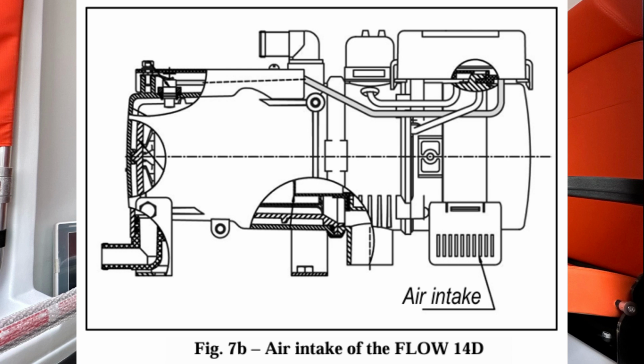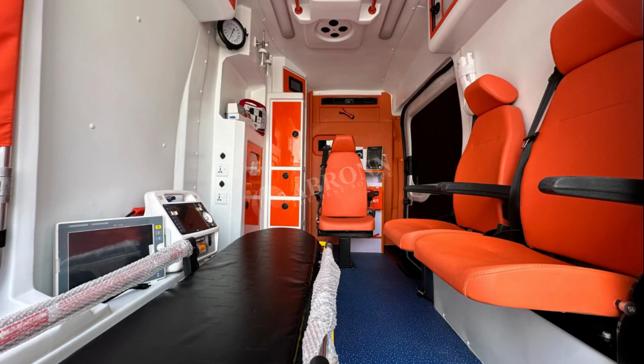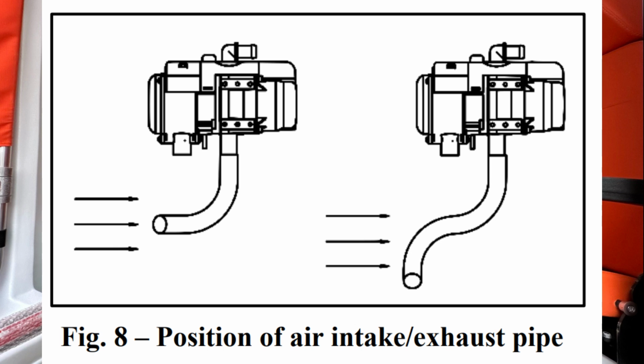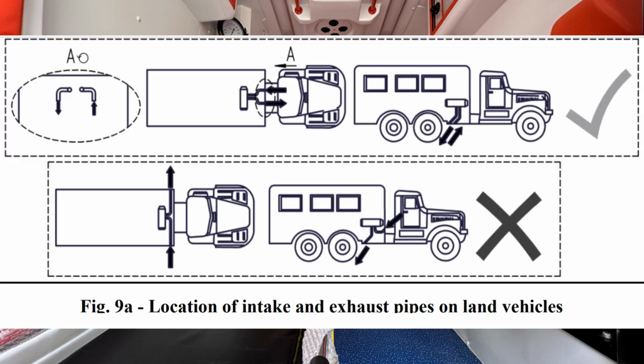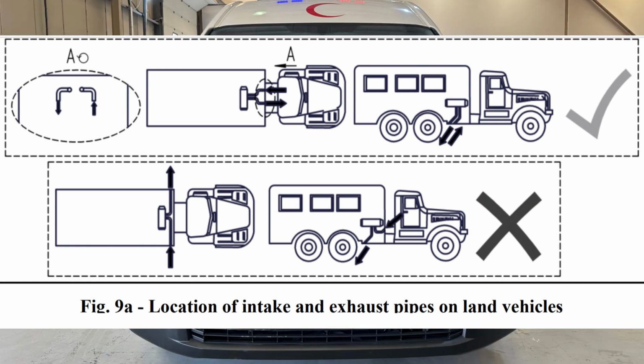The air intake pipe is connected directly to the pipe of the heater and fastened with a clamp, Fig. 7a. When laying the air intake pipe, avoid sharp bends and do not obstruct the opening of the air intake pipe with foreign objects. Make sure the opening is pointing downwards as shown in Figure 8. If that is not possible, a 3 mm hole needs to be drilled at the lowest point of the pipe. The correct installation of the exhaust and air intake pipes is when they are on the same side as can be seen in Figure 9a and b. The distance between them, to exclude the suction of exhaust gases through the air intake, must be at least 20 centimeters.